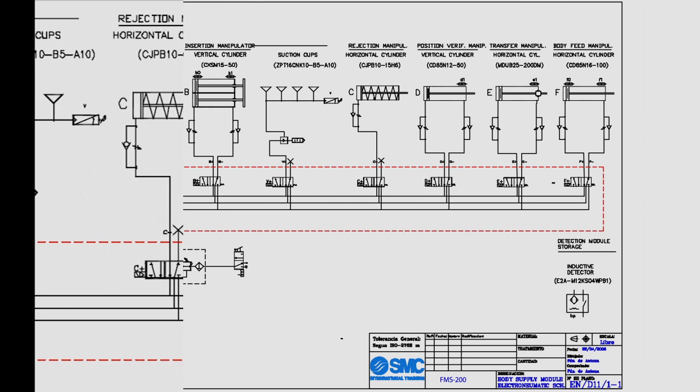And the next cylinder we have is the transfer cylinder, and again it has position information but it only has it on the extend portion of the cylinder. And our last cylinder is the body feed manipulator, and again we can see by here looking that we have position information on both sides so we will know when this cylinder is extended or retracted. Both of those have metering devices on them so we can monitor the speed that it extends at and monitor the speed that it retracts at. And notice the valving here is two position and it has a single solenoid valve. So a signal to extend and then a removal of the signal will automatically force it to retract.